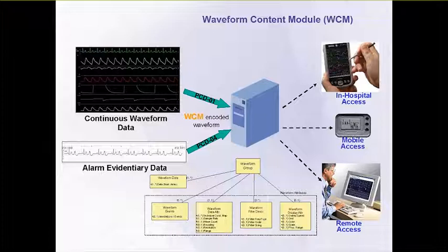This can be sent in two forms. We can receive waveform images or waveform data in two different types of forms. A live streaming waveform can be provided that constantly updates, or content can be recorded into a waveform snippet or an image, including a snapshot of the patient waveform in an update or an outgoing event. Using these two methods, remote monitoring of the patient waveforms can be accomplished via workstations where the live waveform could be seen, or from some smart mobile devices that have web capability or the ability to display image data.